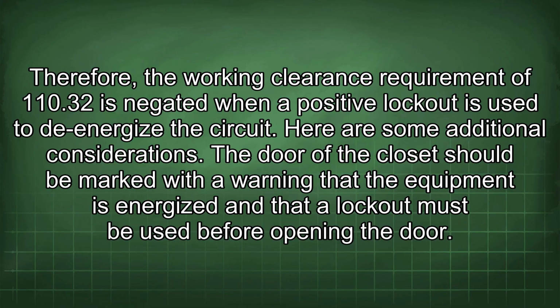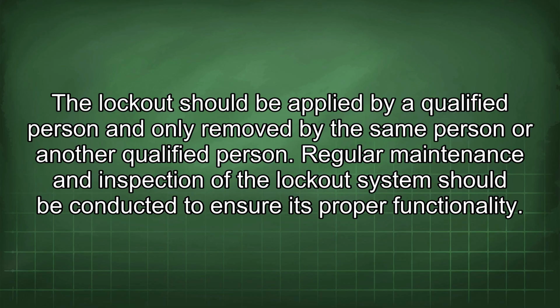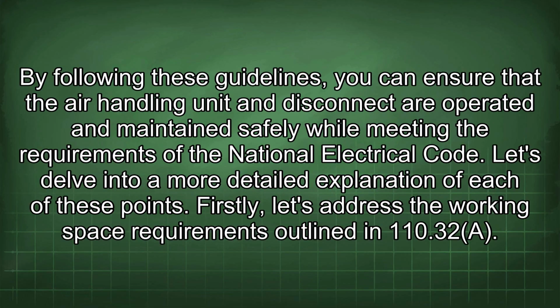Here are some additional considerations. The door of the closet should be marked with a warning that the equipment is energized and that a lockout must be used before opening the door. The lockout should be applied by a qualified person and only removed by the same person or another qualified person. Regular maintenance and inspection of the lockout system should be conducted to ensure its proper functionality. By following these guidelines, you can ensure that the air handling unit and disconnect are operated and maintained safely while meeting the requirements of the National Electrical Code.